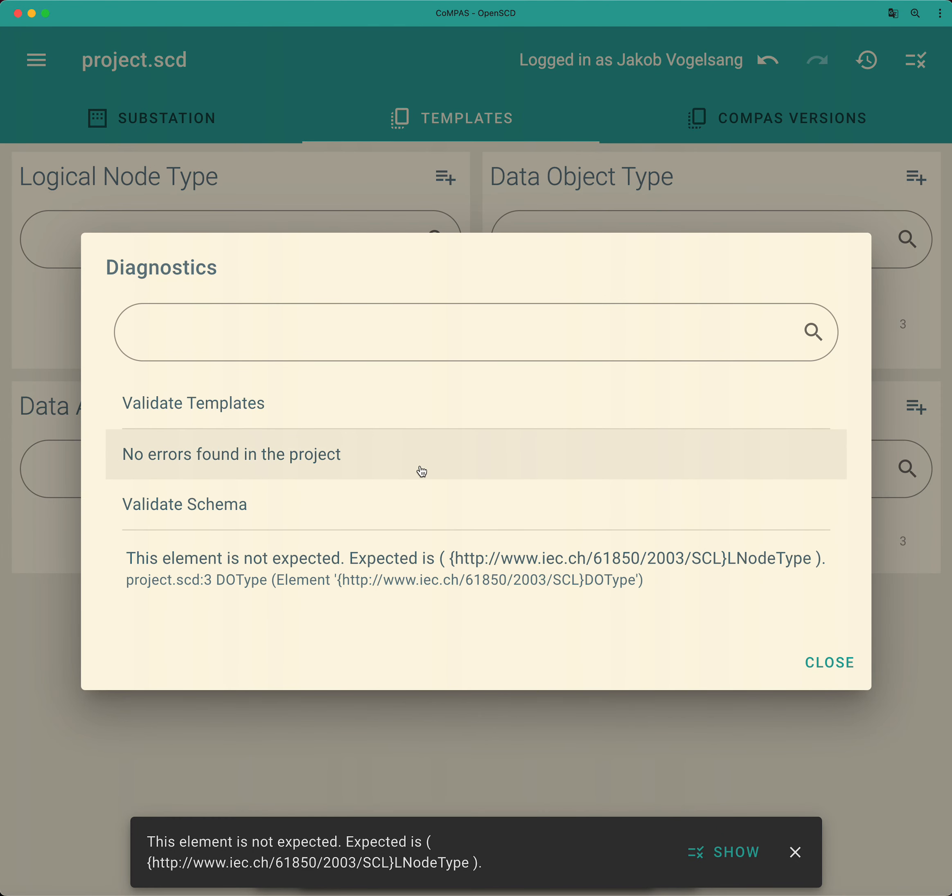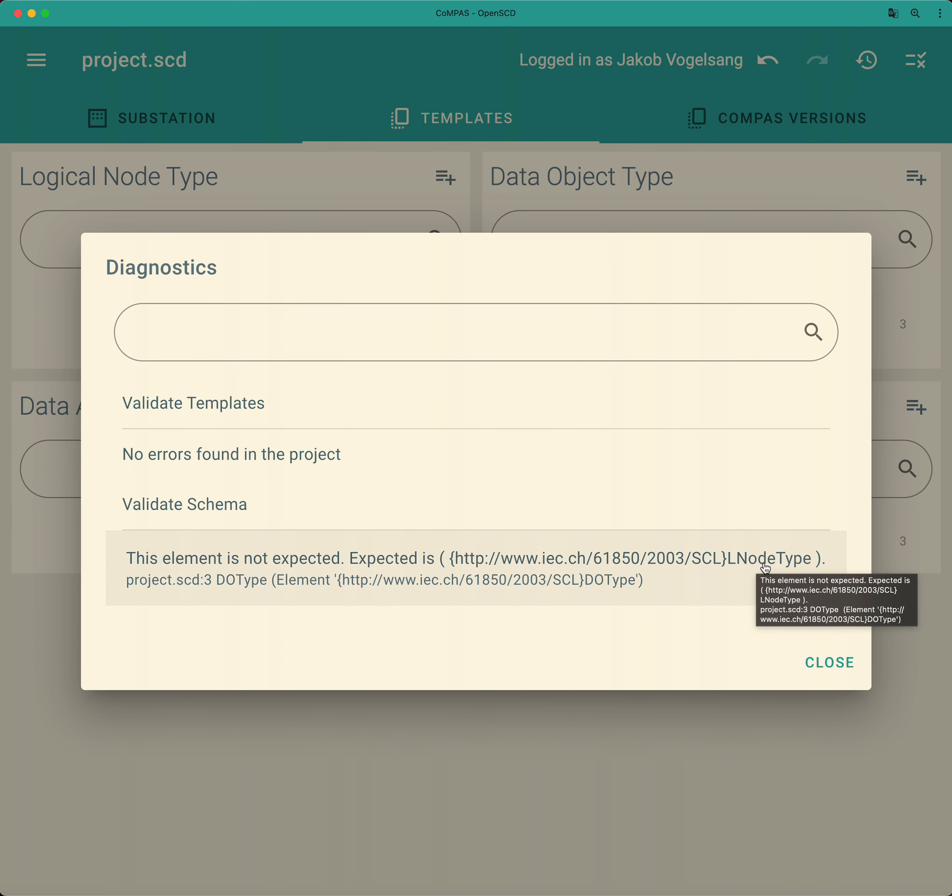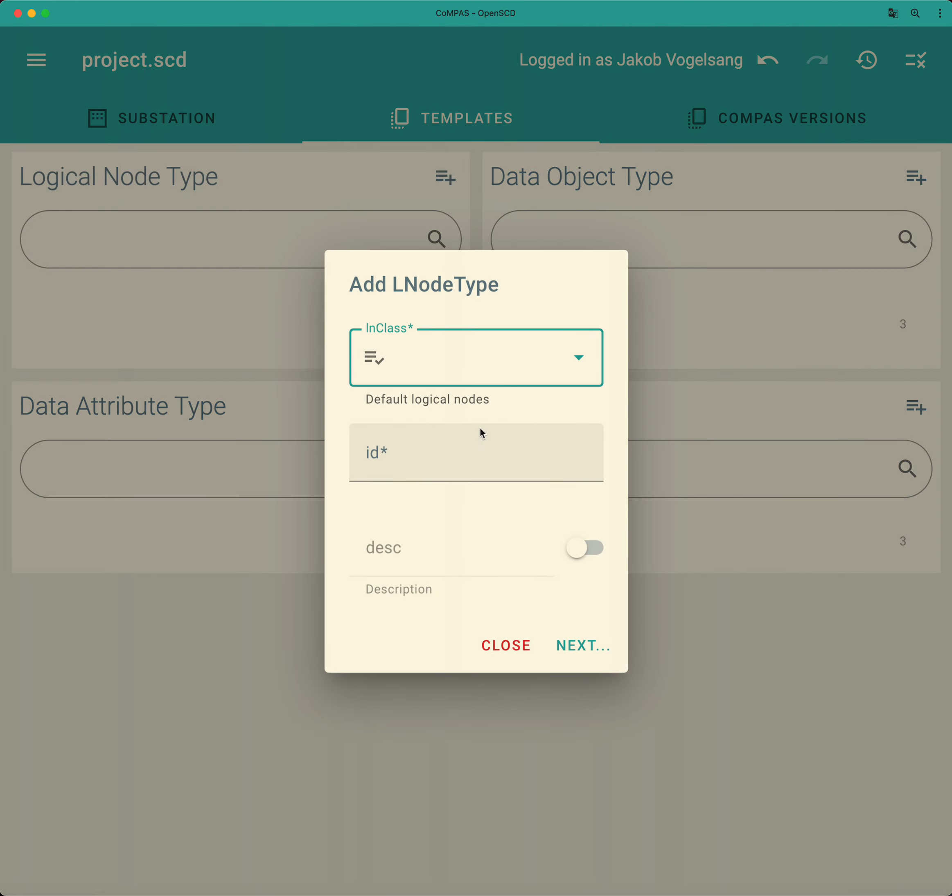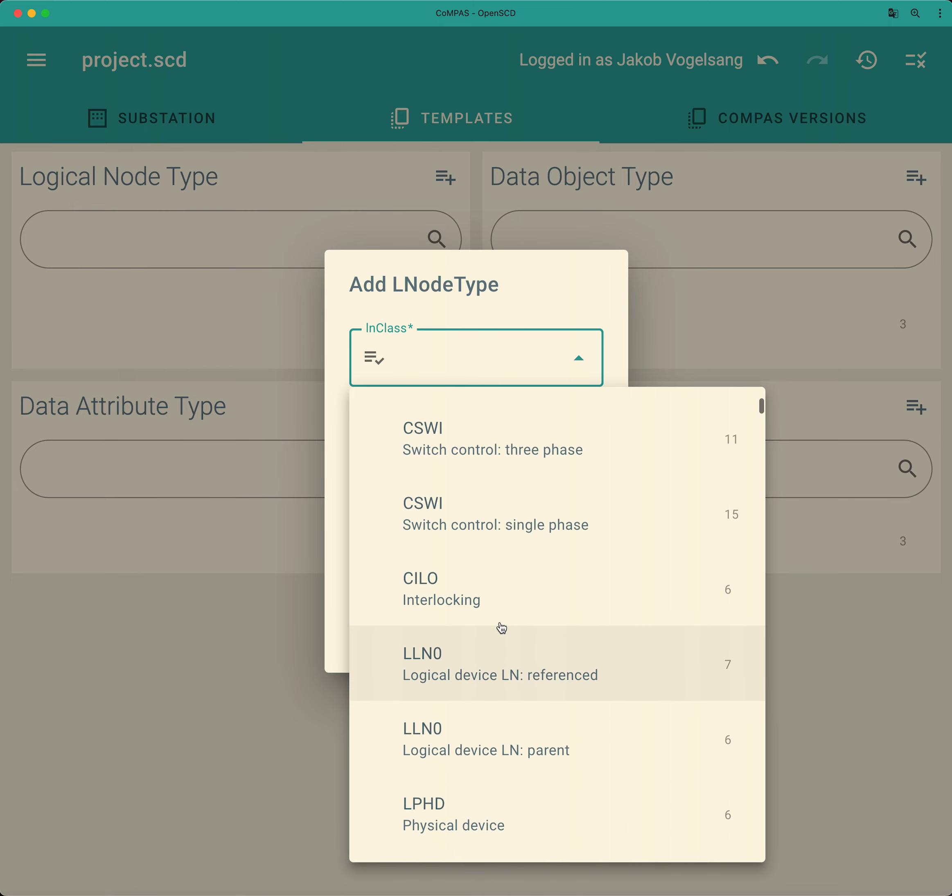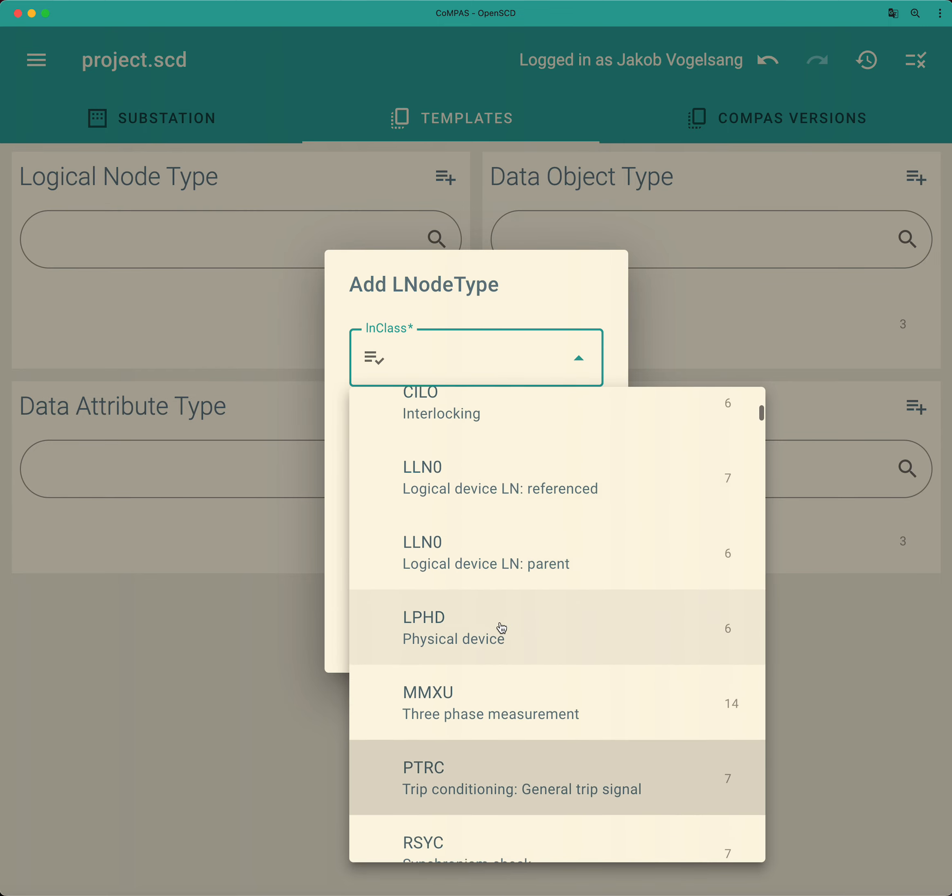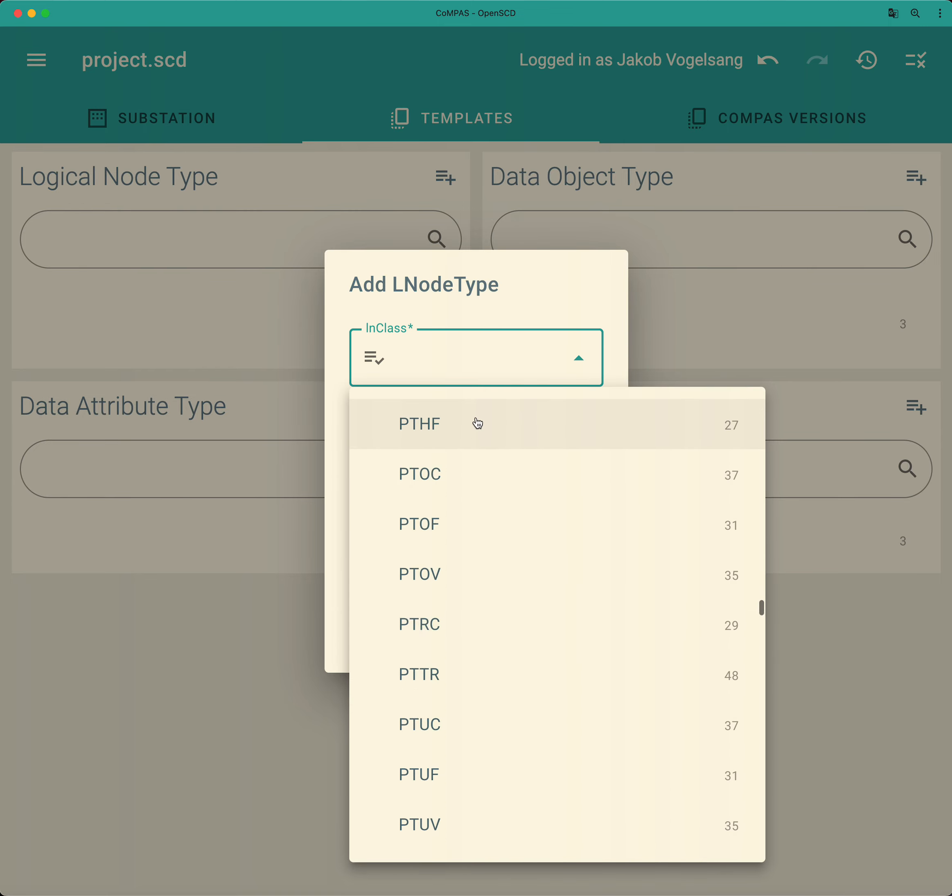Okay, so no errors found in the template so far, but we have a schema validation problem that says there must be at least one logical node type in the data type template section. Okay, let's add that. So we said that we want to add a PTRC class and we don't want to add it from the template ICD but we want to create a new one.